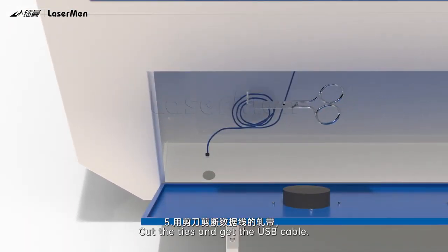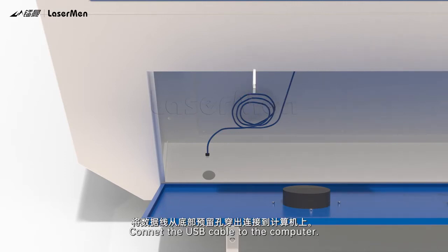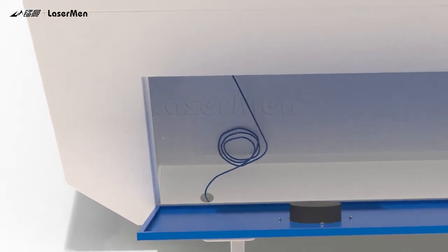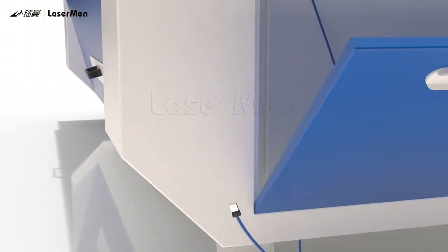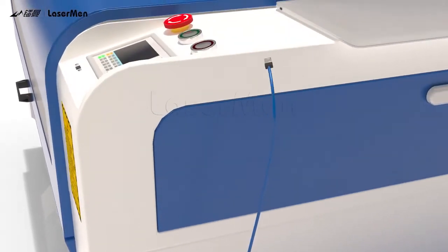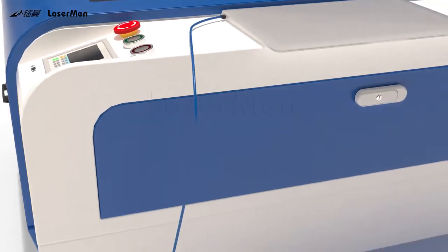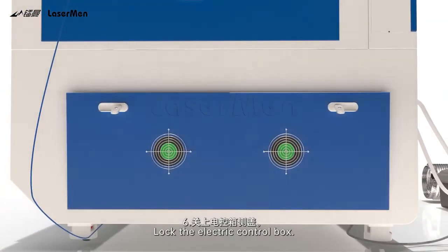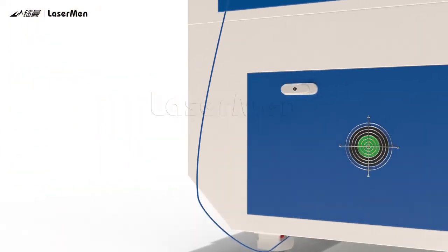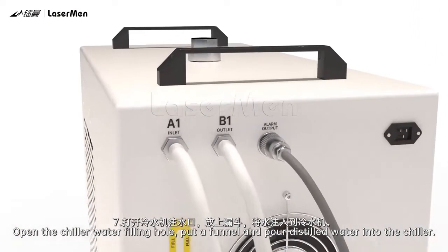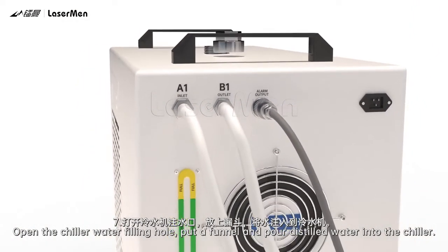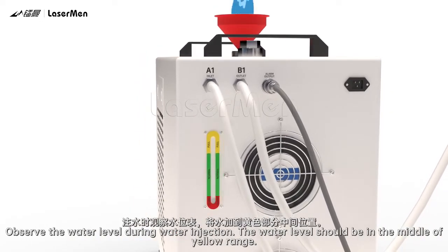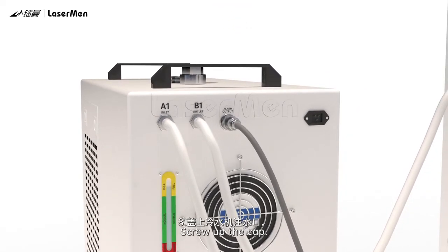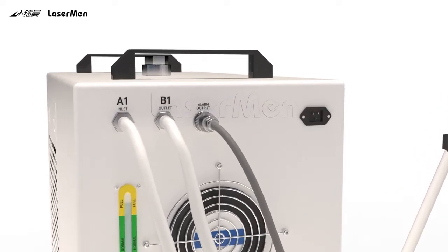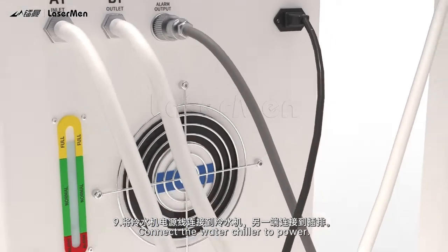5. Cut the ties and get the USB cable. Connect the USB cable to the computer. 6. Lock the electric control box. 7. Open the chiller water filling hole. Put a funnel and pour distilled water into the chiller. Observe the water level during water injection. The water level should be in the middle of the yellow range. 8. Screw up the cap. 9. Connect the water chiller to power.